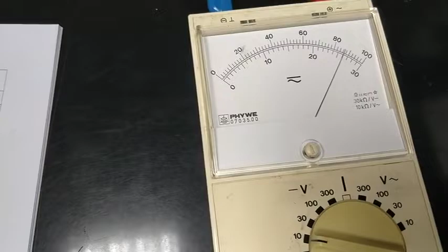If we reach 1 kilovolt, we have to switch to the next range, otherwise our readings will be saturated, so we won't take a reading there. I'll switch now since I'm already very close to 1. Switching to the next range means every 10 will now equal 1 kilovolt, so instead of multiplying by 100, we'll multiply by 1000. You can see the reading is now very low, close to 1, but it's low because it will be multiplied by 1000 instead of 100.